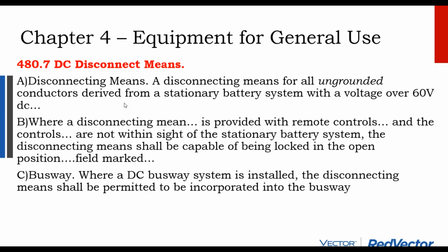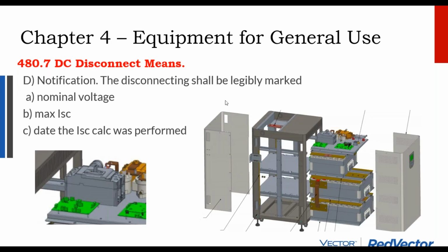And so we get to item B, and it says where a disconnecting means is activated via remote control, and the controls for the battery disconnects are not within sight of the battery system, whatever disconnecting means you have needs to be locked in the open position. So, if someone could be remote controlling the battery disconnect in another room, then where you're required to have a battery disconnect, and that would be one of those cases, the battery disconnect needs to be able to be locked in an open position. So generally common sense stuff. The disconnecting means shall be legibly marked with nominal voltage, current rating.